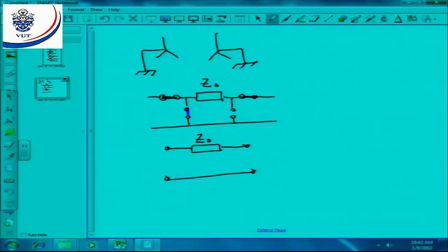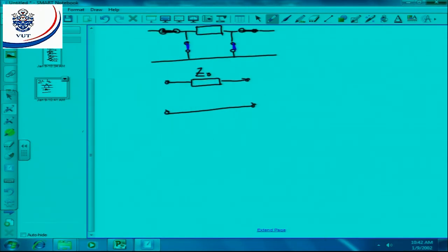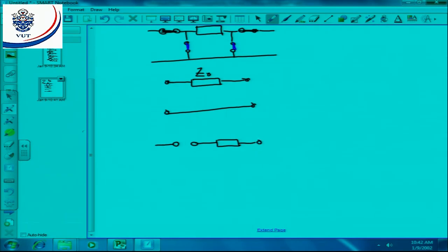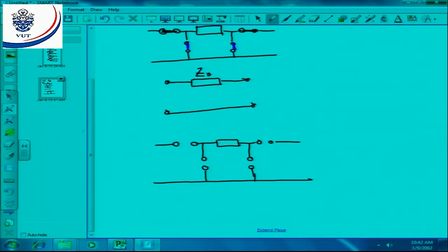A dash and A dash are closed if the respective winding is delta-connected. So for a delta connection, those links are closed. However, you can see these other links are open, and therefore no zero-sequence currents will be able to flow. This is the most important part — the configuration of the switches determines whether zero-sequence current can flow.